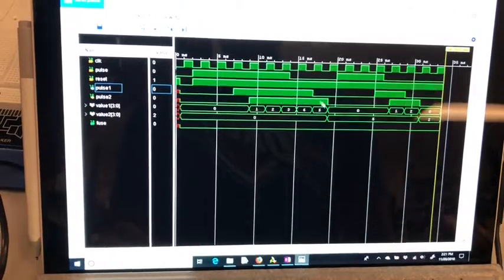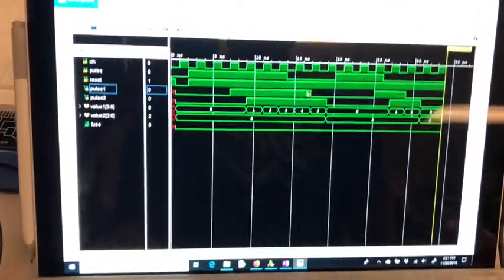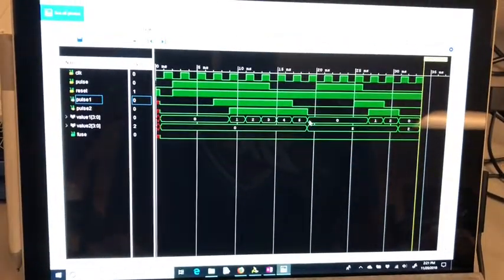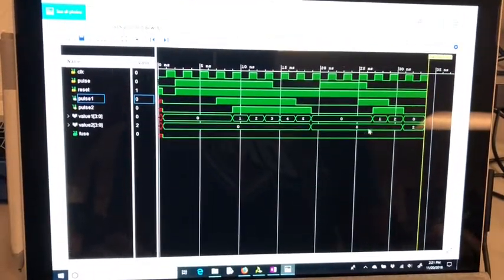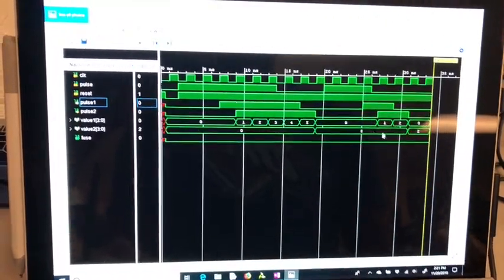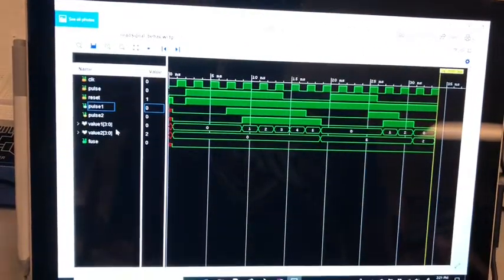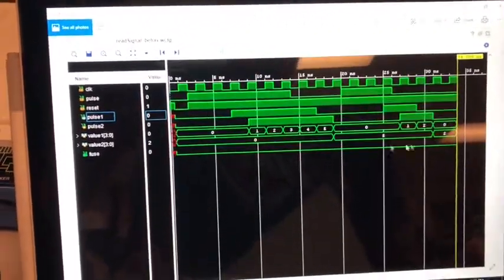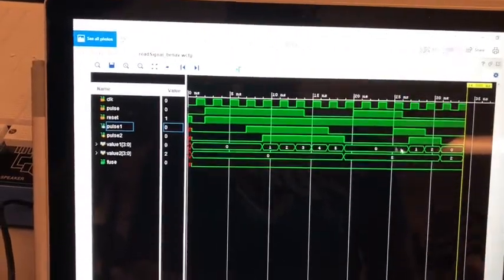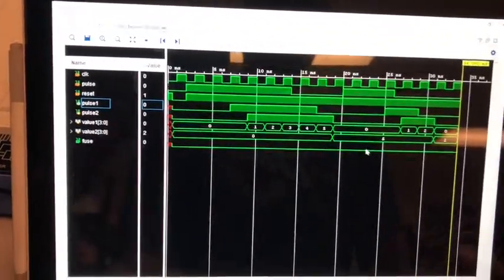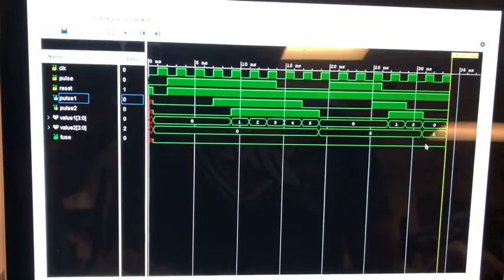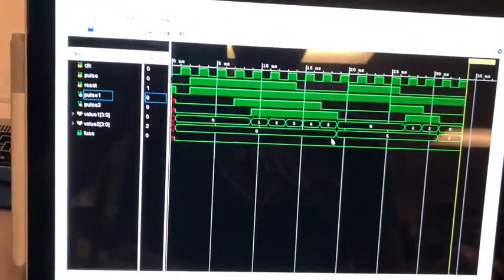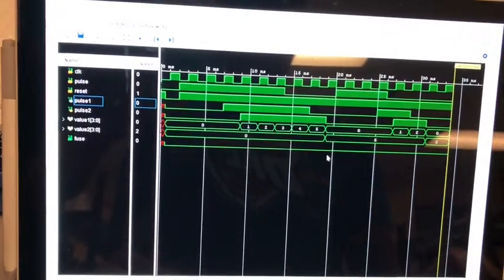This drop off here is our cutoff for the length of our pulse. At the end of our pulse length, value 1 is passed to value 2, and value 1 resumes counting the length of the pulse. This value 2 is then compared to our parameters to determine whether there's a fault or not. If the value 2 is over our measurement, it sends a fault. If it is under, then no fault is sent. Here, fuse sends a 0 or 1 signal to signify whether we have a fault or not.